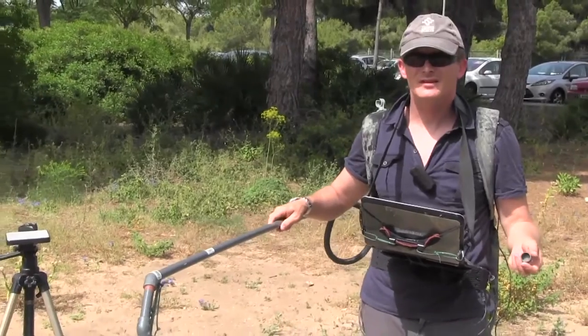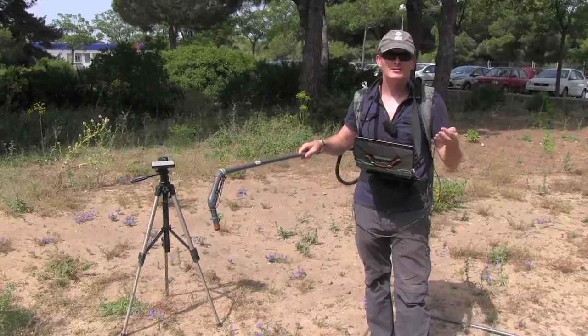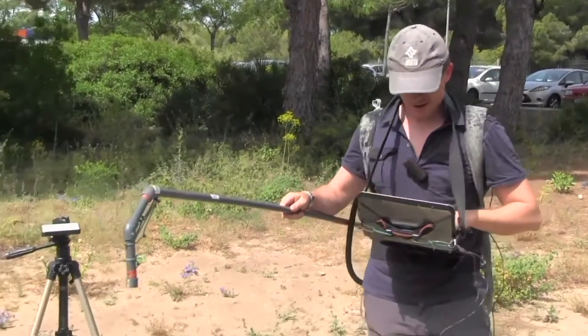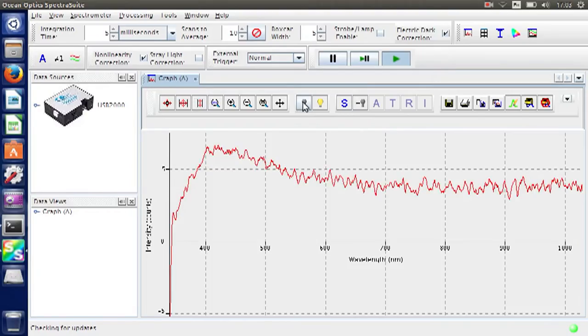The process begins with a small calibration where we take account for the dark signal. The dark signal is basically the noise of the instrument. The thing to be careful with is that the dark signal is affected by temperature, so if you're out in the morning and things warm up, it's worth taking the dark signal once or twice during the day. To take the dark signal, we simply blacken the tip, make sure there's no light coming in, then on the machine we say take a dark measurement and store the dark measurement.